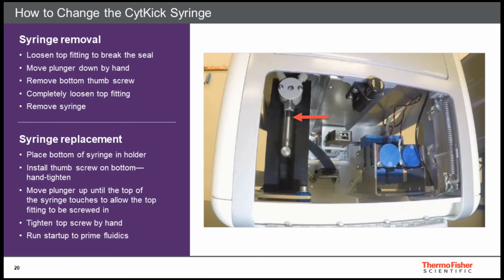If working with CytKick or CytKick Max, changing the syringe is slightly simpler. Simply loosen the top fitting to break the seal, pull the plunger down by hand, remove the bottom thumb screw holding the plunger, and unscrew the syringe the rest of the way out. To install the new syringe, install the bottom part of the syringe first by securing the thumb screw, finger tightening it. Next, move the top part of the syringe up until it can be screwed in and tightened. It is always good to check that the syringe fittings are still tight after running a few startup scripts.